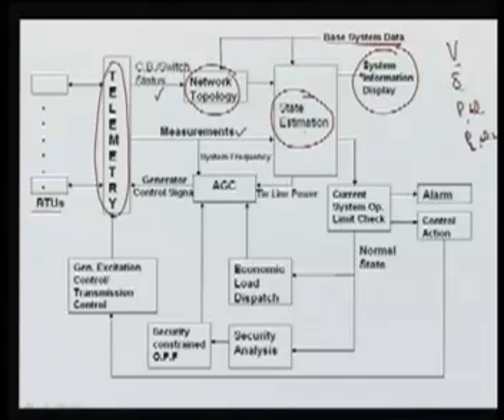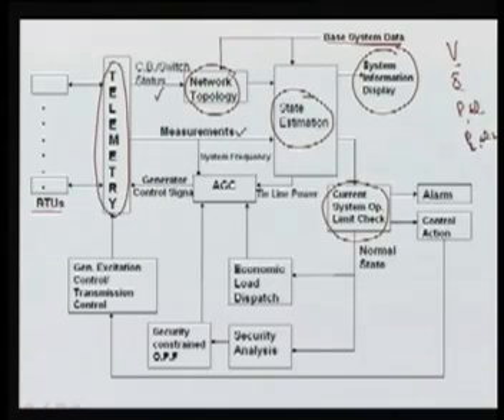This state estimation information is used to check the current operating state of the system. For the present power system, we are measuring the data which is coming through the RTUs, through the network topology and the state estimation, and here the current system operating limits can be checked.